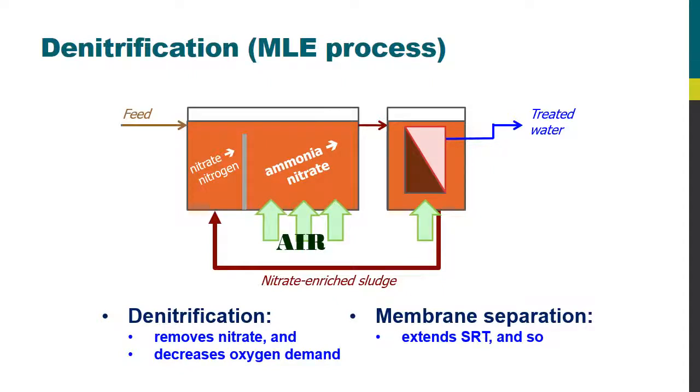But what it also does is extend the solids retention time to allow slower growing microorganisms to develop. And those microorganisms which are slow growing happen to be the nitrifiers, the things that convert ammonia to nitrate, and actually the denitrifiers as well. So you tend to get more nitrifiers developed in an MBR process than in a classical activated sludge process, such that you get rather better nitrogen removal for an MBR than you do with the classical process.